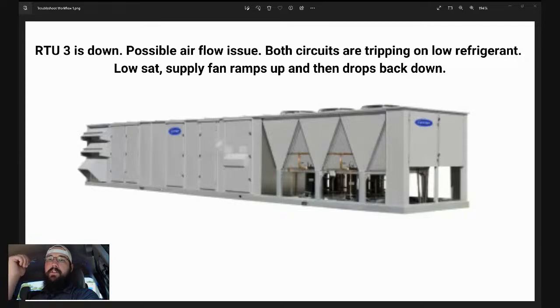we have to think about, okay, what's a basic sequence of this unit? One, we have to have a start from the building. Then we have to call our fan on and get that up. Well, the fan runs off of static pressure, so we need to make sure that we meet that static pressure and can maintain it with our drive. Then once we see that our leaving air temperature is not cold enough, we've got a high leaving air, it starts looking at how many compressors I need to bring on, or let's start staging compressors on and bring that supply air back down, right? So this is the super basic sequence here.